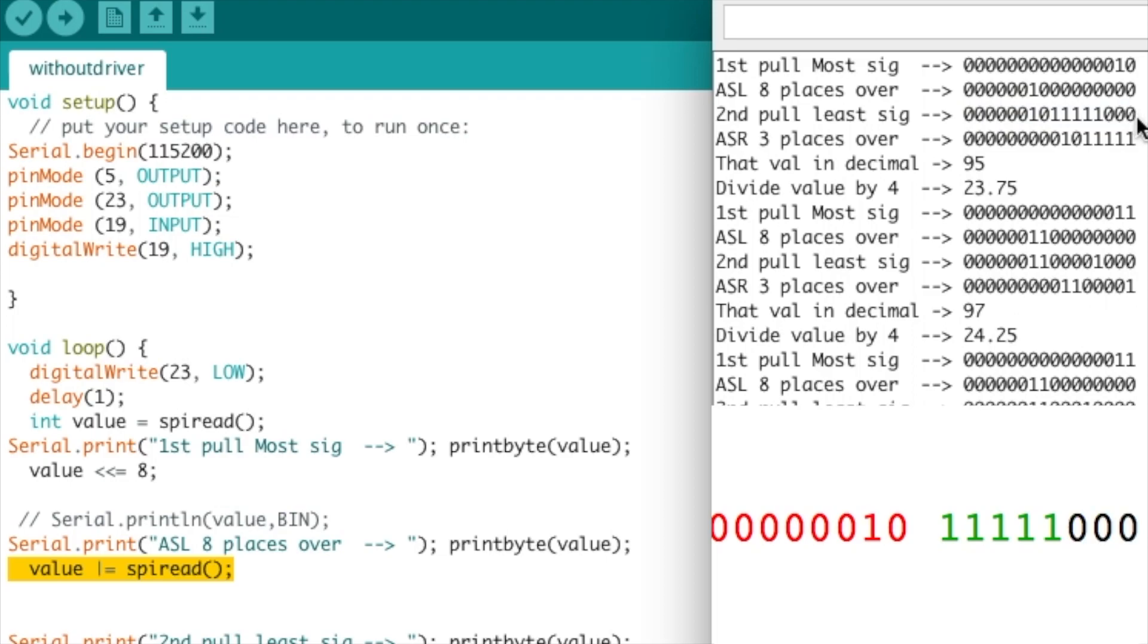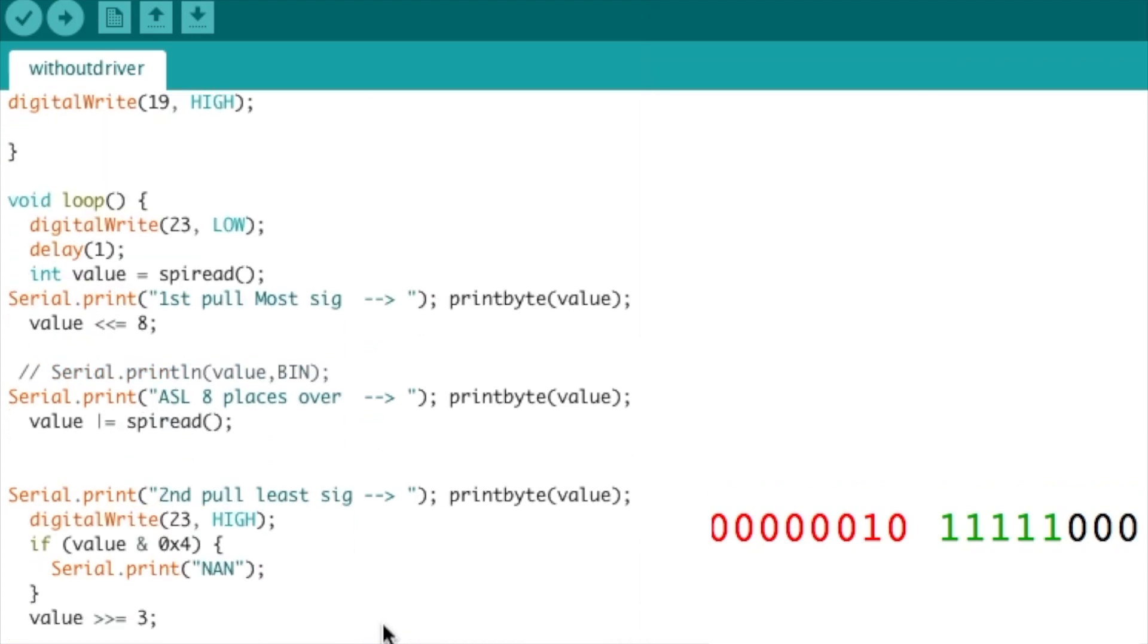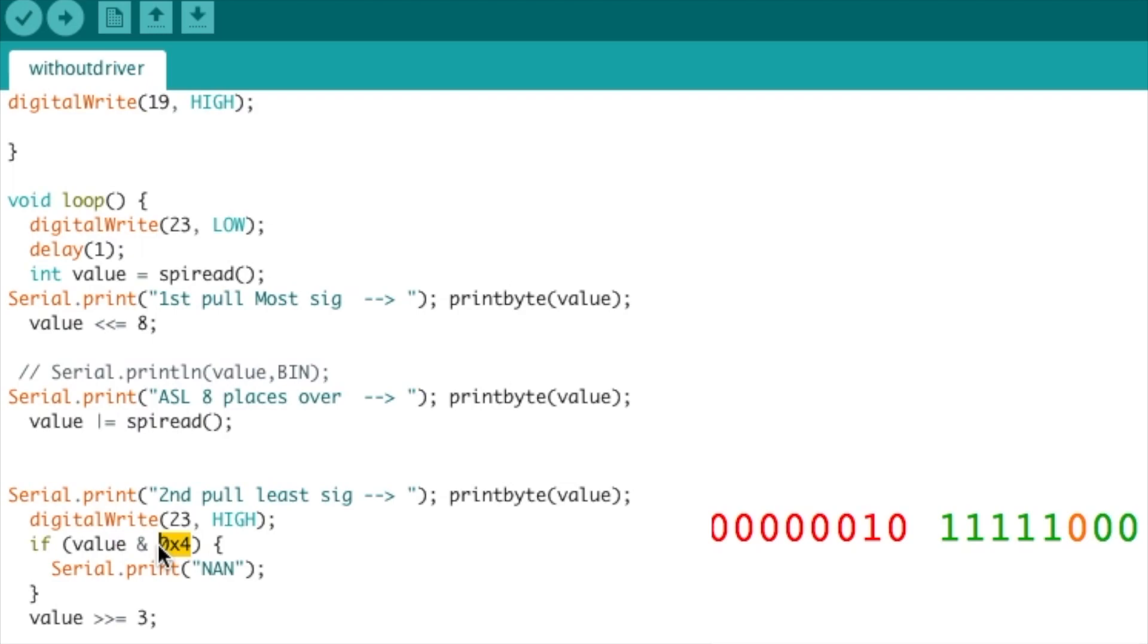Once we were left with this value, we have to know from the data sheet that the first three values do not represent temperature values, they have a different purpose. If we look here, we could see that the third value specifically has to do with connectivity of the actual sensor at the end.